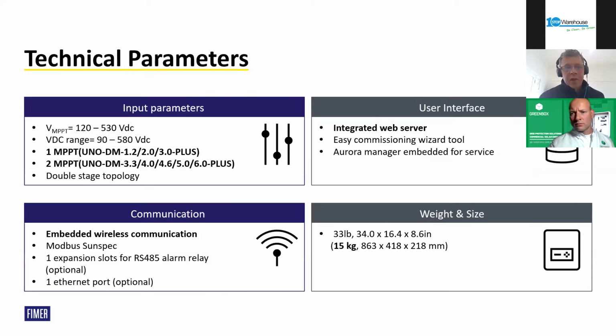Some of the technical features for the UNO-DM-PLUS: a wide working range, 90 to 580 volts DC. This is due to the double stage topology, which broadens the working range of the DC side, ideal for shady or cloudy conditions. One of the benefits of double stage topology is there's no correlation between grid voltage and the DC working range. In single stage topology inverters, when the grid voltage rises, the minimum DC working range rises with it. Double stage topology eliminates that, giving a true indication from the data sheet of what's achievable on the DC inputs.